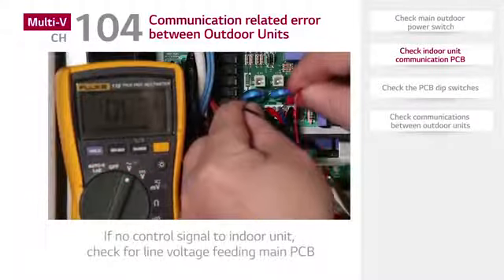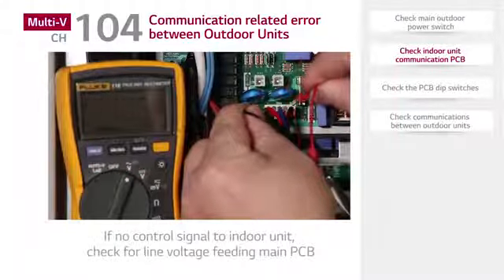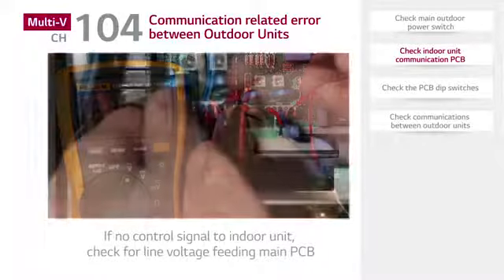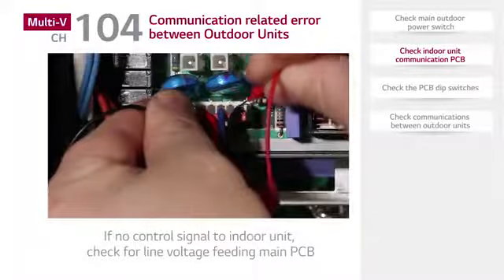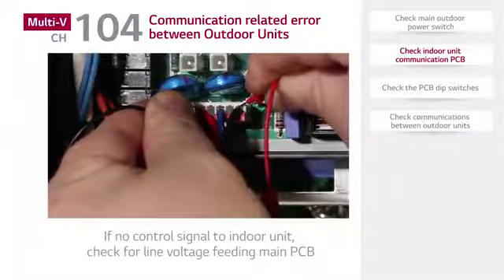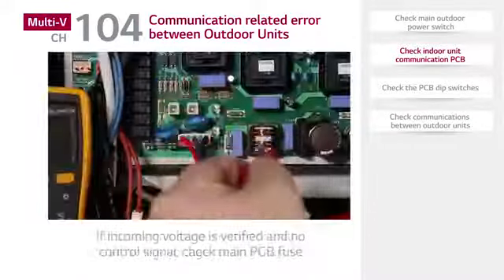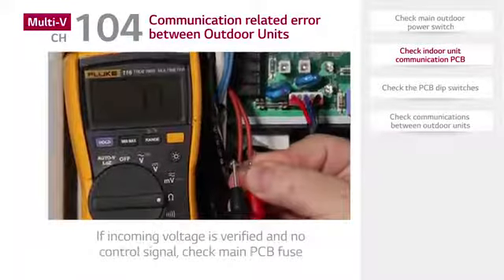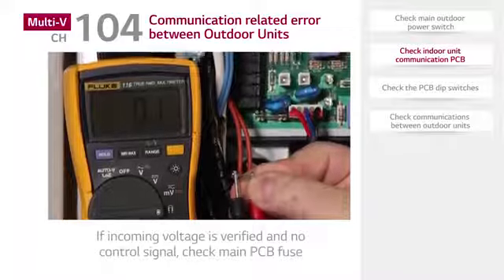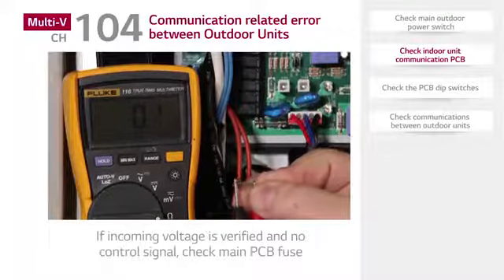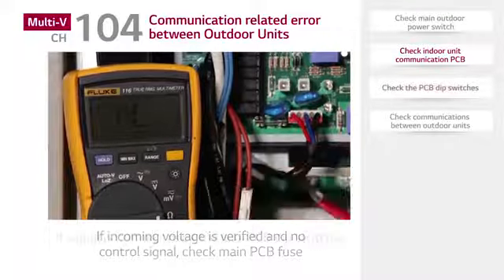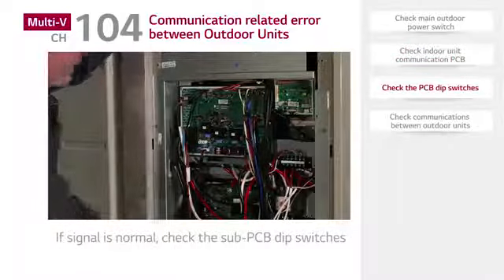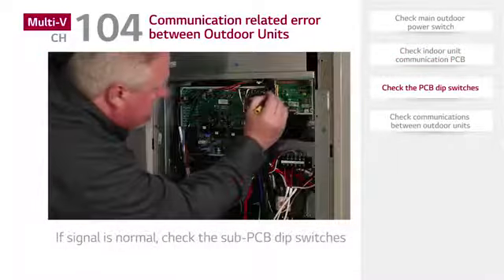If there is no communication signal to the indoor units, check for line voltage feeding the main PCB. If there is no incoming power to the main PCB, inspect the filter PCB. If the incoming voltage is verified and there is no control signal, check the main PCB fuse. If the fuse tests good, replace the main PCB. If the signal is normal, check the sub-PCB dip switches.